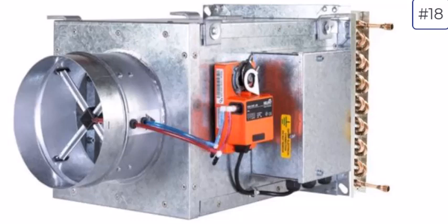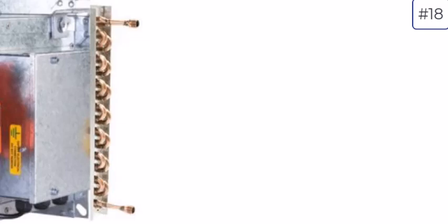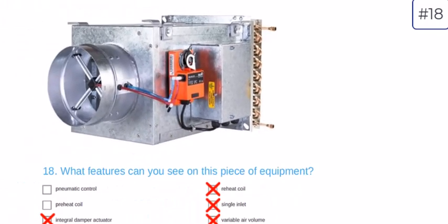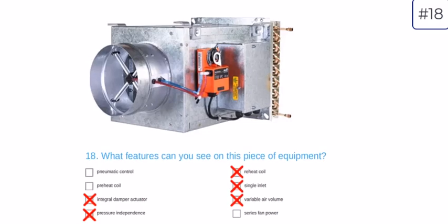No special fan, no series or parallel fan box. We do see a reheat coil on the downstream side of this box. So this is a pretty vanilla thing that we would see. I'm guessing everybody watching this video has one of these in one of their buildings.